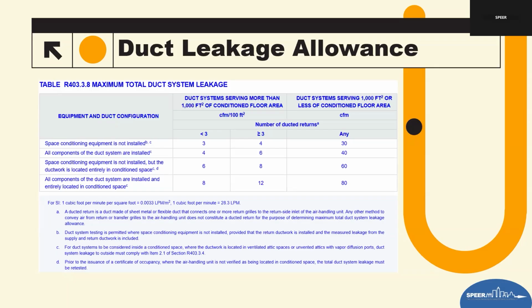No equipment installed, 30. Equipment installed, 40 if it's outside of conditioned space. No equipment installed, but it's inside conditioned space, 60. Equipment installed, and also inside conditioned space, it's 80. So that is a big difference, and in my opinion a very helpful allowance for trying to get small systems and small dwellings to pass.